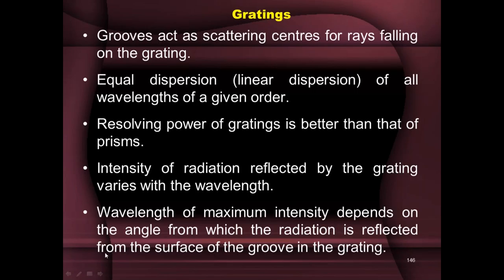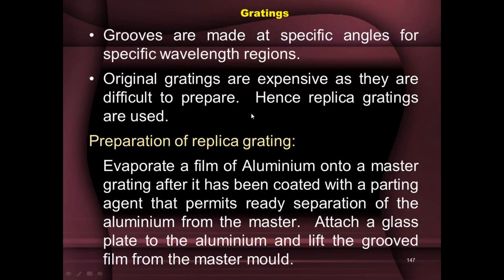The wavelength of maximum intensity depends on the angle from which the radiation is reflected from the surface of the groove in the grating. So the angle at which the groove is made is very important — it decides which wavelength will have maximum intensity, and as you move away from that wavelength, intensity goes on reducing. Grooves are made at specific angles for specific wavelength regions. For UV-visible and IR, the angles and number of lines differ significantly.